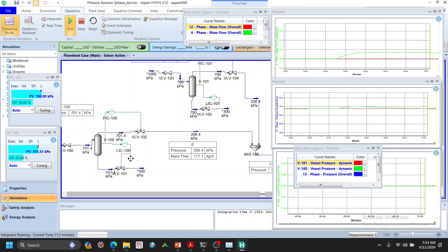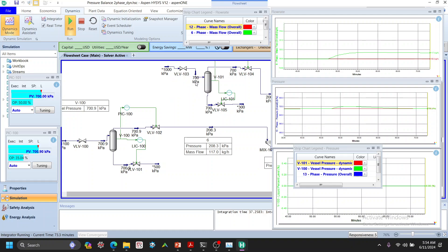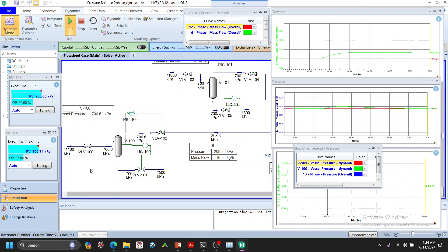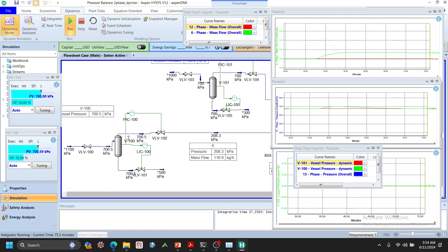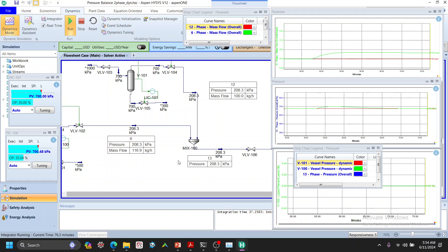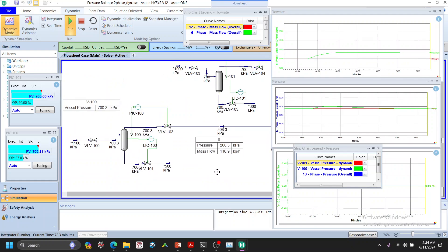With higher upstream pressure, the delta-P across this path is about 300 kPa — for a flow rate of around 100 kg/hr. But for the other vessel, the delta-P is now 400 kPa because of the increased source pressure. Because of this higher delta-P, more fluid flows continuously through stream 6. We can see stream 6 has stabilized at 117 kg/hr, up from 100 — that's the effect of increasing source pressure.